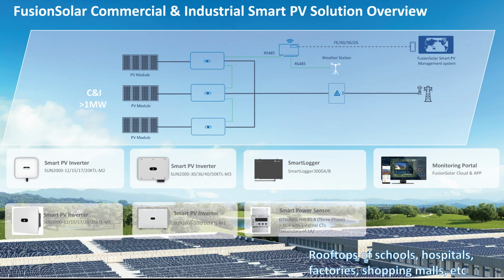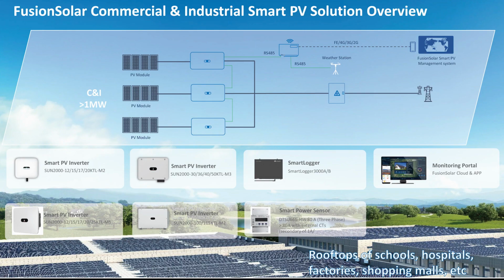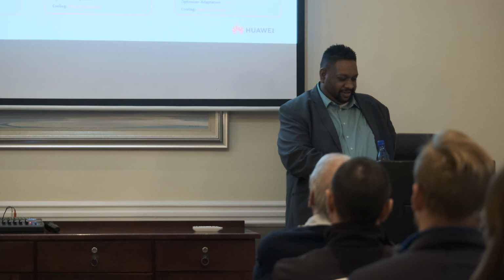Greater than 1 megawatt, this is the solution or string diagram that you see. You have your inverters connected in parallel on the AC side, which is then connected to the load, which is then connected to the grid. And here you also have what we call a smart logger. For anything greater than 1 megawatt, we suggest having a smart logger, which communicates with all the devices as well as the portal. It can also communicate with accessories like weather stations and so on. Basically, this is for rooftops of schools, hospitals, factories, shopping malls, etc. The largest shopping mall now is about 6.8 megawatts rooftop. It's a mall in Richards Bay, not with Huawei.